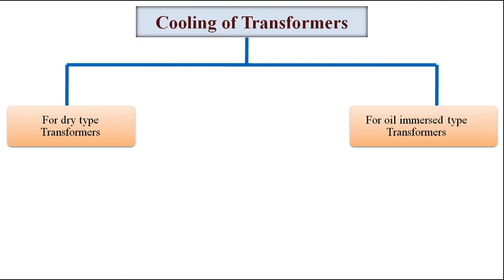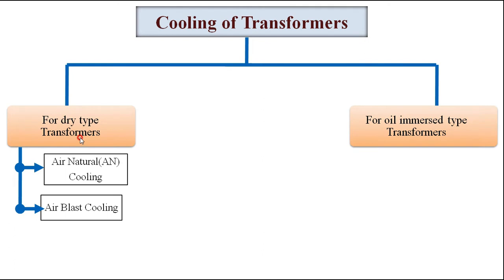In the dry type, the assembled transformer is not immersed in oil in a tank. Whereas in the oil immersed type, as the name itself suggests, the assembled transformer unit is immersed in oil. For the dry type transformer, we use two different methods: one is air natural cooling, in short called AN, for small capacity transformers. The other method is air blast cooling.